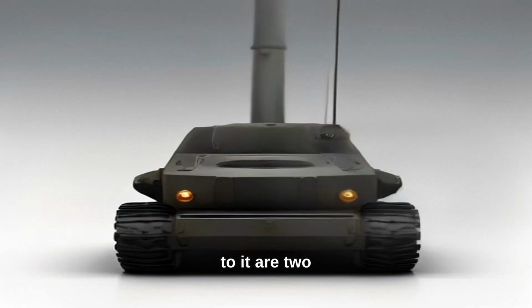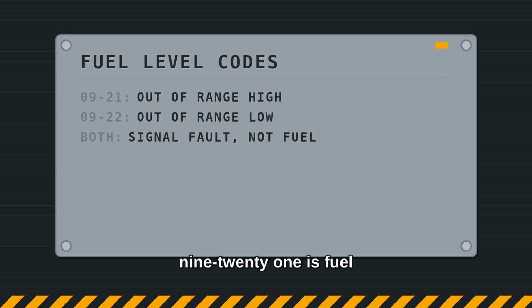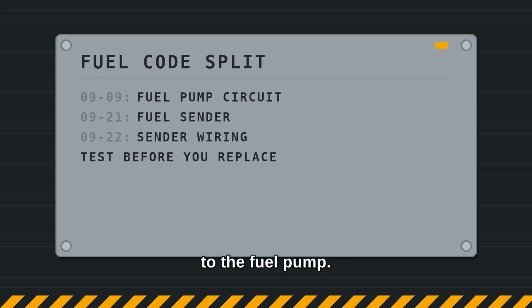But sitting right next to it are 2 codes that look similar and mean something completely different. 921 is fuel level out of range high. 922 is fuel level out of range low. Out of range doesn't mean empty. It means the signal itself is impossible. It's a kitchen thermometer reading 400 degrees. The number isn't low, it's nonsense. So 99 sends you to the fuel pump. 921 and 922 sends you to the sender and its wiring.